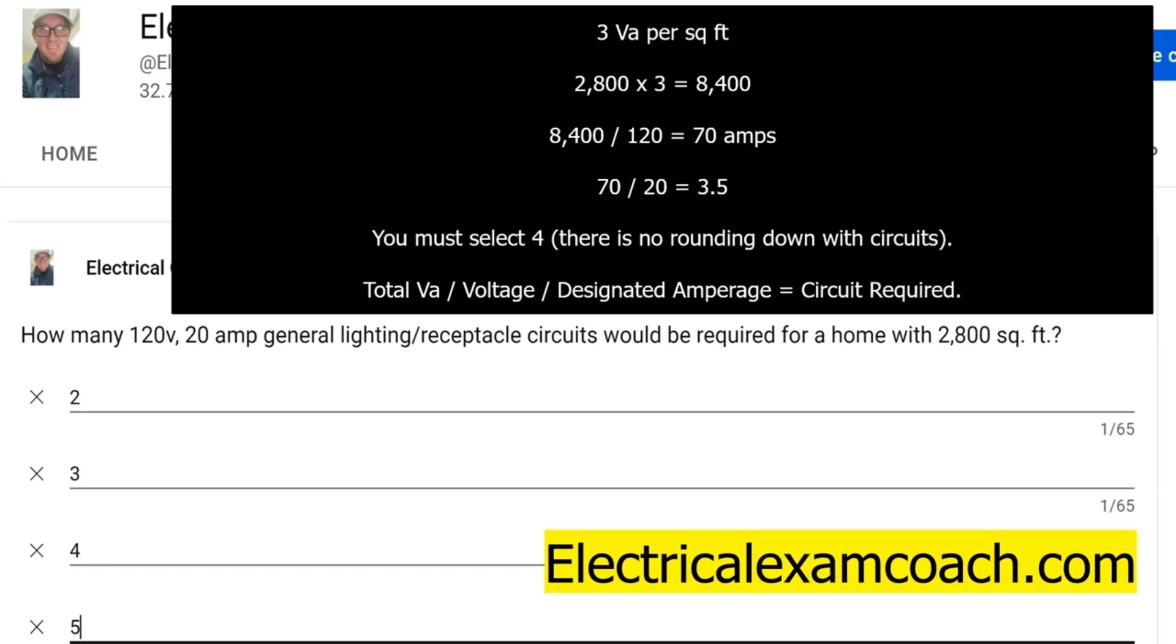When we divide that out, that's going to give us 3.5 and we must select 4 and round up, because there is no rounding down with circuits. You can't have a piece of a circuit, so anything above 3 is going to go up to 4. It's total VA's divided by voltage, divided by designated amperage, and that equals the circuits required.